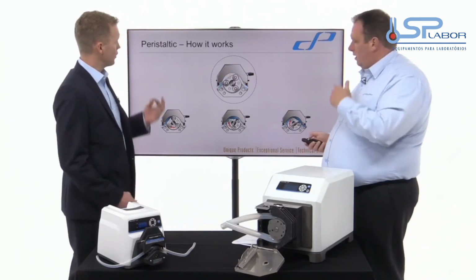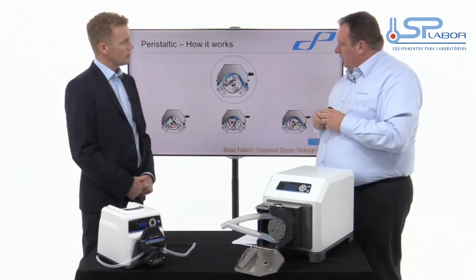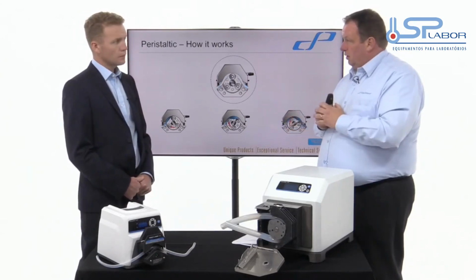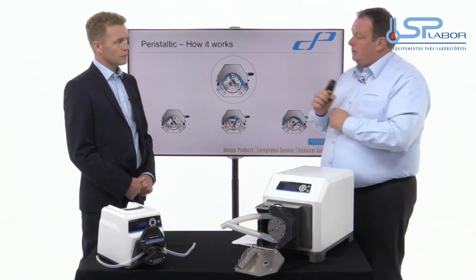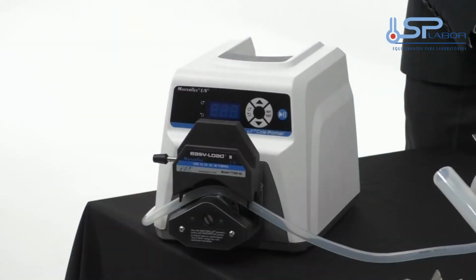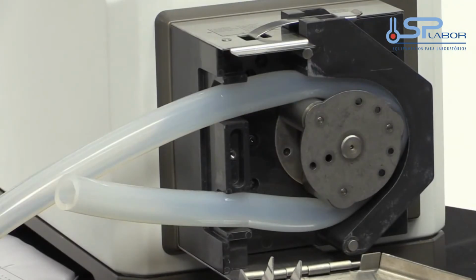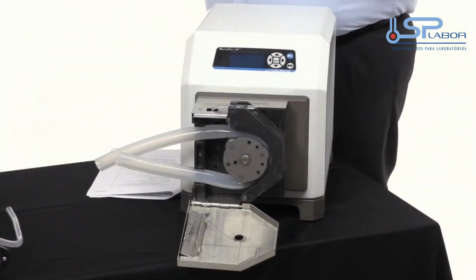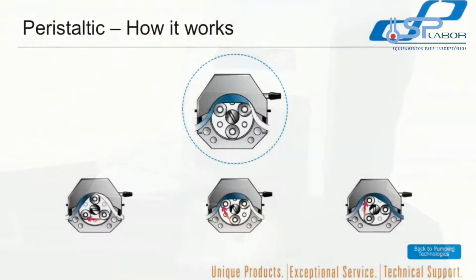And what are the maintenance requirements for a peristaltic pump? This is one of my favourite points: minimal. The wearing component is the tube. It's a consumable, so you will have to change it, but that's the only item. We can get up to 10,000 hours life out of certain tubes in certain conditions, which is several years runtime. The motors and the pump heads, I've known them to go on in excess of 10 years, so the actual drive and control gives a very good working life, doesn't have any issues.